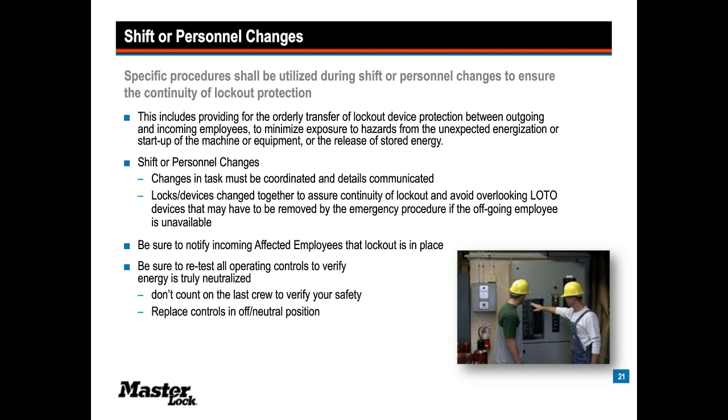And it's really important when handing off lockout responsibilities from shift to shift to make sure that retesting takes place on the incoming shift. You would like to have the assurance that the first crew did properly isolate everything and test to zero energy. However, if they didn't, the idea that their locks are in place and you're just hanging your lock and going to work is a false sense of security.